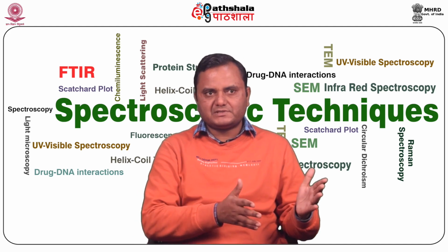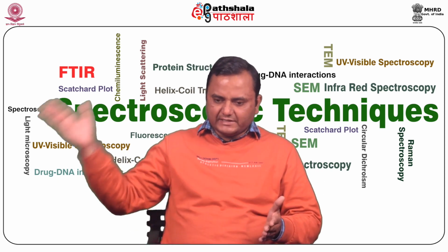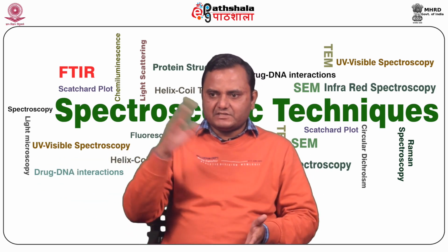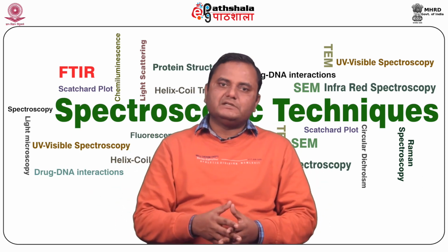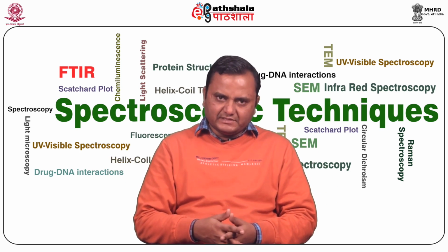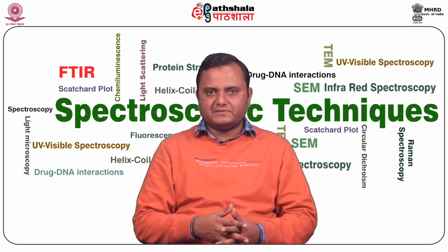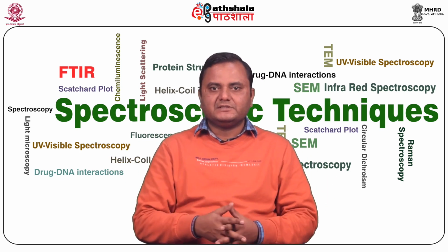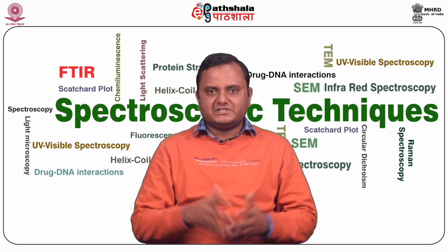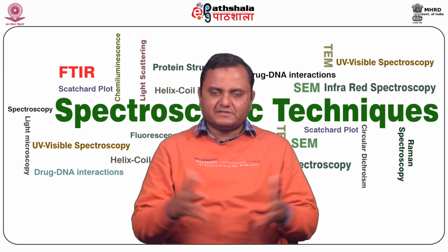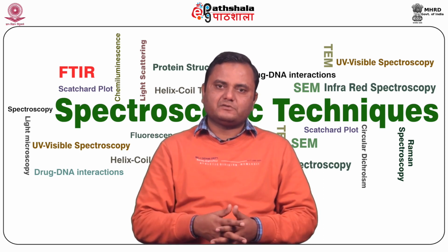Once you know the absorption wavelength, then you can directly select the absorption or excitation wavelength, and then you can collect the emission spectrum, and vice versa. You can fix the emission wavelength and then scan the absorption wavelength. In both ways, the two monochromators help to select the particular wavelength of light for excitation and emission. So the excitation light then passes through the sample chamber, which contains the fluorophore in the cuvette, and that is what is detected by the spectrofluorometer.